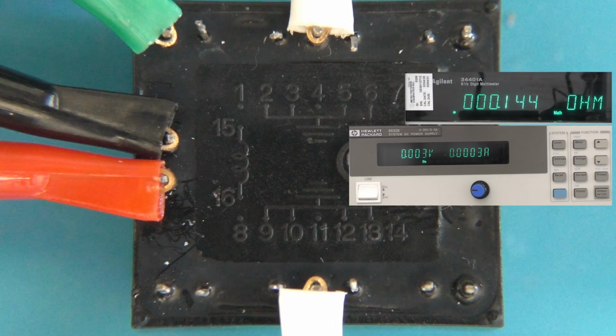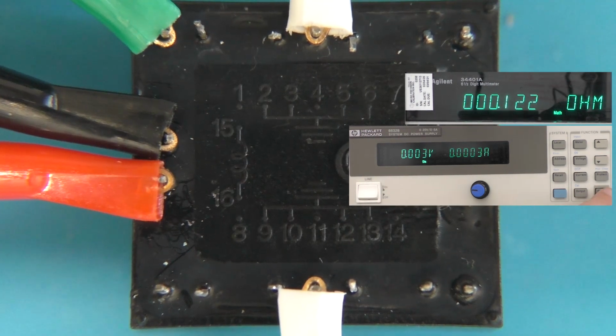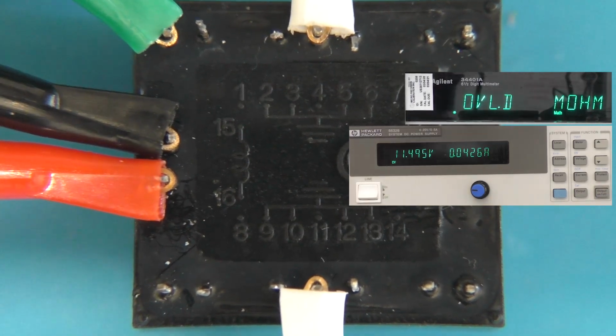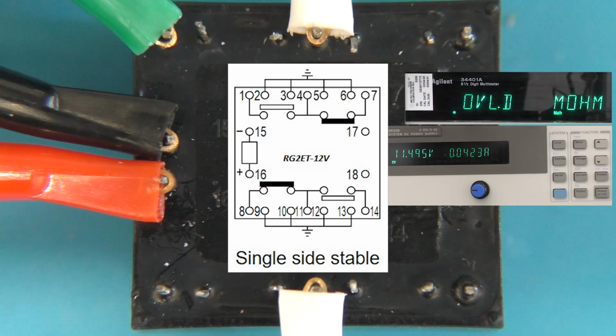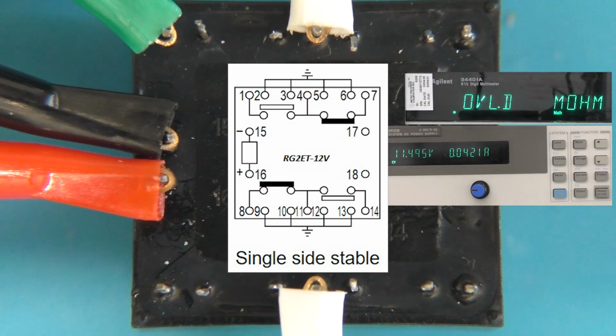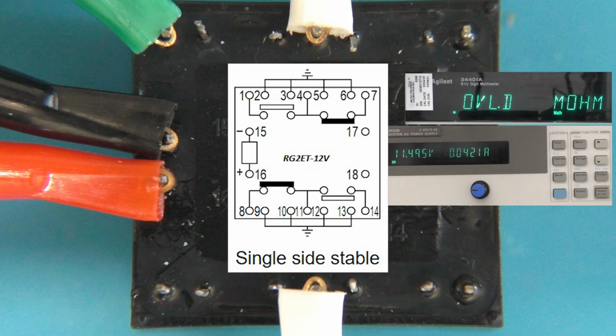The green clip is connected to the DMM ground. The green clip is on pin 1. With the power off, we have a resistance of 0.1 ohms across pins 1 and 4. Pin 1 should be the normally open pin, but clearly this is closed. When we apply 11.4 volts to the coil, the pole opens on pins 1 and 4 and we see high impedance. This does not match our standard relay, as pins 1 and 4 should be closed under power.